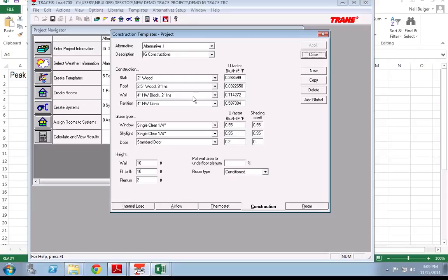It's very important on walls, if you have a minute to think about what it is you're looking to run, that you get a wall type that isn't just the U value it should be, yet it's also a wall type that has around the right mass the building actually has. The model does take into account lag of mass, and that is a key element to making the model work correctly. Now, if it's not in there, your model will do some very strange things, or just be inaccurate and not good for anyone.